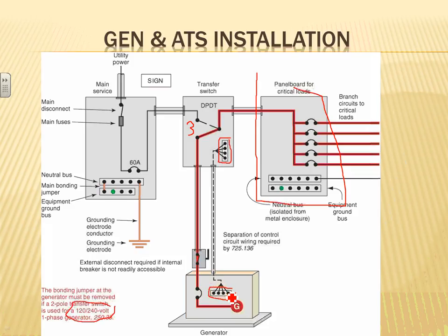Yeah, and they allow you transition when you want to switch your transformer or your generator online to street power or something along these lines. It's still there, so you can have parallel. And since the emergency system can be out for 10 seconds based on the code, you can go open transition for cheaper equipment.